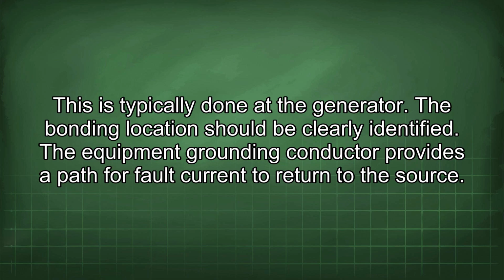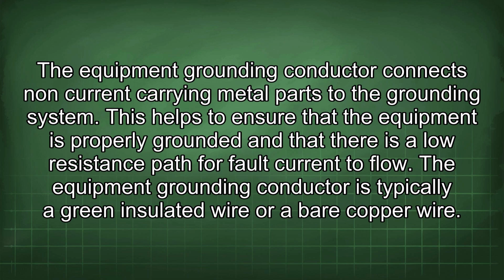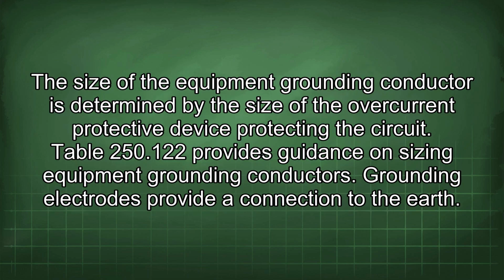The equipment grounding conductor provides a path for fault current to return to the source. The equipment grounding conductor connects non-current carrying metal parts to the grounding system. This helps to ensure that the equipment is properly grounded and that there is a low resistance path for fault current to flow. The equipment grounding conductor is typically a green insulated wire or a bare copper wire. The size of the equipment grounding conductor is determined by the size of the overcurrent protective device protecting the circuit. Table 250.122 provides guidance on sizing equipment grounding conductors.